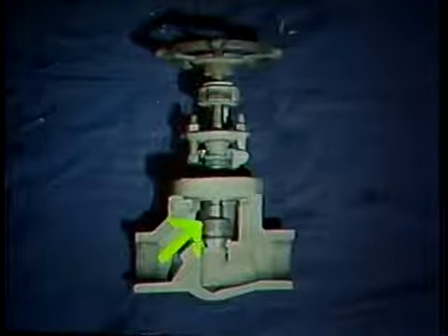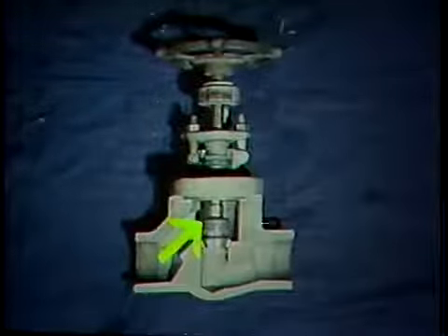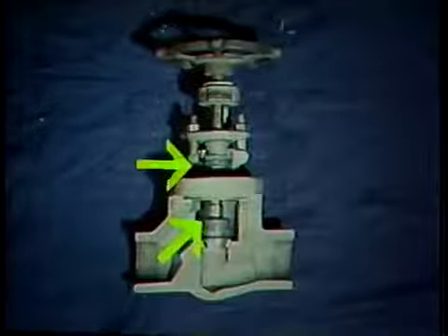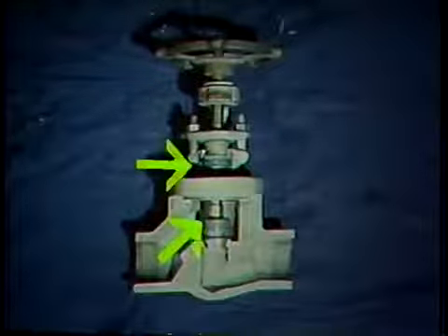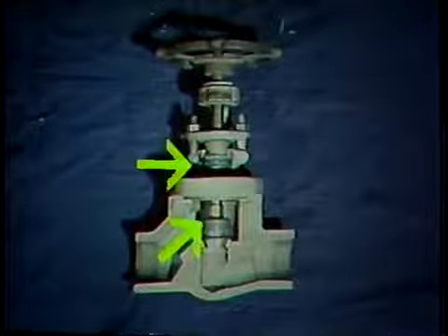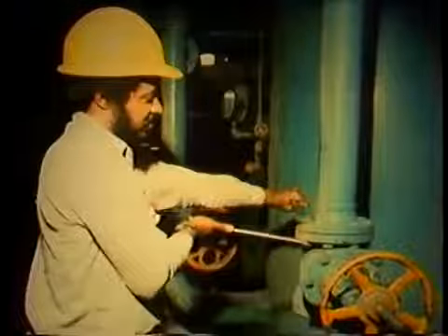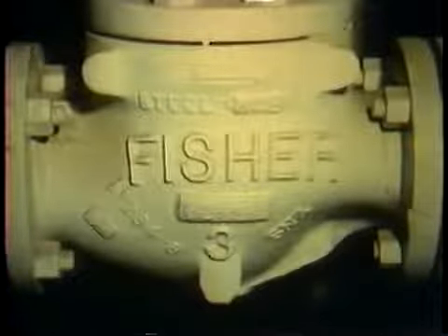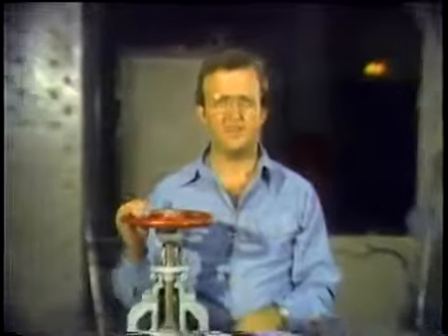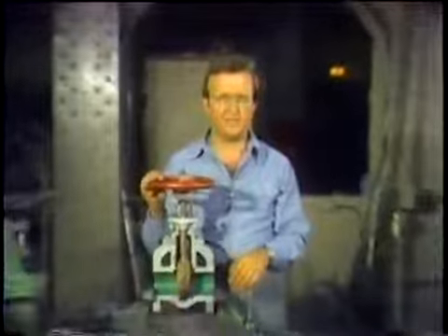If the valve were installed incorrectly, the other way around, there would be pressure on the packing when the valve is closed. In this case, there could be leakage that would require more maintenance. Careful installation is very important for the proper operation of the valve. The bridge wall markings will help you make the correct installation as well as tell you the arrangement of the parts inside the valve.